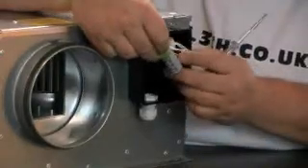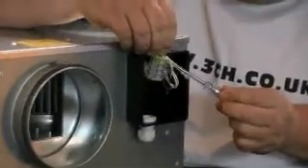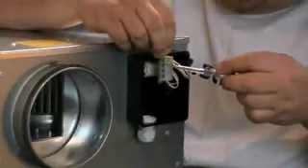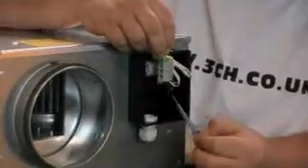All you have to do then is make sure that the earth is in the left hand side of the two blocks for the earth. So you've been putting it in the left hand side on this side — earth, live and neutral. It's pretty straightforward. We're going to be coming up through here, connecting them into that, and then reseating the electrical block back onto its seating. As you can see, this is the unit fitted now, with the wire elbow holding the wire nice and solid in there so it doesn't get moved about while you're moving the fan around, and it's all wired into the respective blocks.